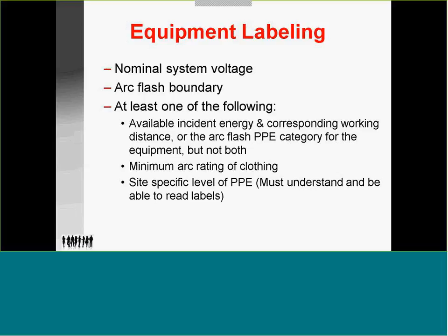Nominal system voltage, arc flash boundary, and one of the following: available incident energy. Remember, incident energy is in calories per square centimeter, corresponding with working distance. The arc flash PPE category for the equipment, but not both. Minimum arc rating of clothing. Now we get into a little hassle with companies. Unfortunately, when the code first came out in 2009 and was adopted, they called it fire-resistant clothing. Now they call it arc-rated clothing because fire-resistant was misconstrued. Fire-resistant clothing may not be arc-rated, but arc-rated is definitely flame-resistant. So you've got the clothing for the particular rating in calories. It'll give you a maximum, what it might be. Specific level of PPE: you must understand and be able to read labels.